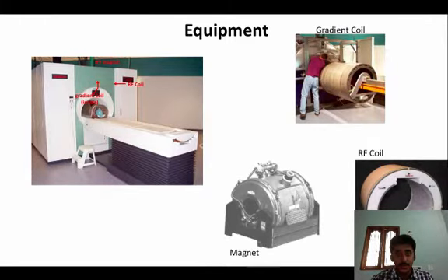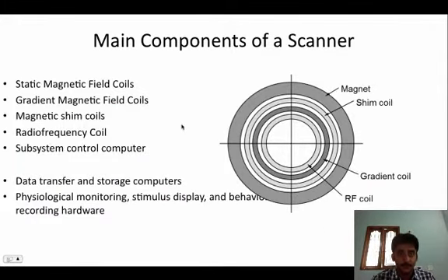So how do we design this MRI machine? This is the heart of our subject. We are actually designing a sensor for magnetic resonance imaging, which is based on magnetic resonance. So our MRI is basically a sensor. How do we build this sensor? It's very easy. It has a main magnet, which is used for the excitation magnetic field, and we have a gradient coil and a radio frequency coil. Let us see the functions of each of these coils.